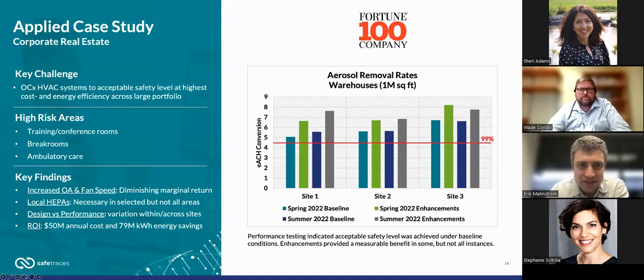What we found was that increasing outdoor air and fan speeds often had a diminishing marginal return given the size of these facilities, many of which had high ceilings. Increasing outdoor air was very cost and energy intensive, and in many instances didn't show much particle removal benefit. Local HEPAs were useful in some of the smaller, more enclosed areas with lower ceilings, but certainly weren't necessary in many other areas.